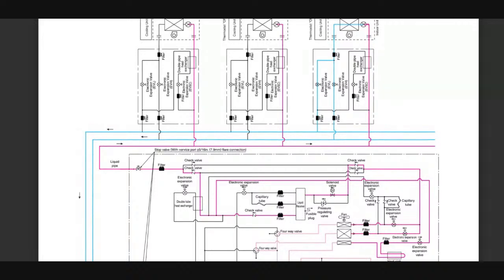Right here. Stop valve with service port. So the stop valve with service port is referencing the physical isolation valves, the little king valves or ball valves. They're just calling them stop valves, right? Are those open or closed? That's all they're asking. That's right there. That's what we pipe into when we first turn everything on and pull our vacuum from and everything else.